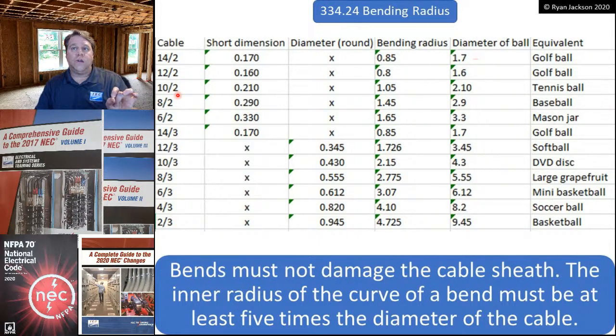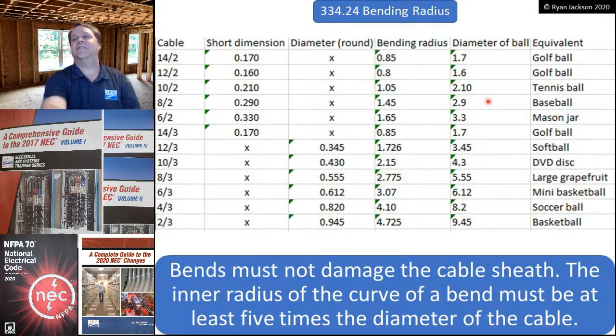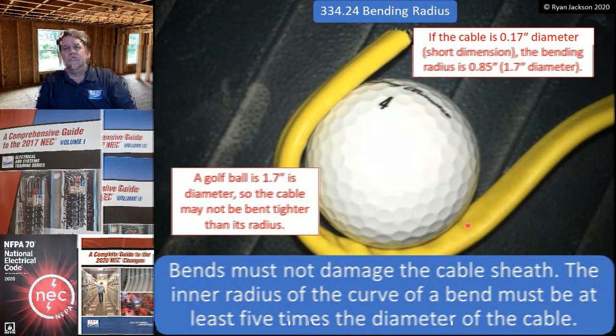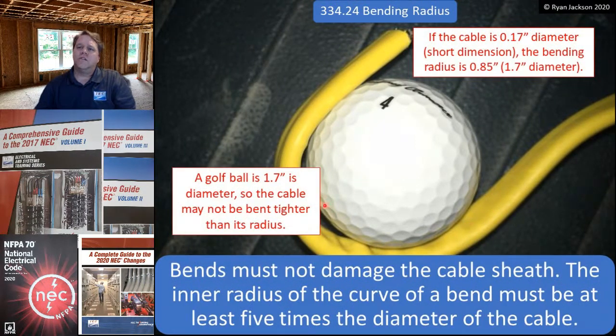If I had 10-2, that's similar to a tennis ball. So if this was 10-2, don't bend it tighter than a tennis ball. And baseball for 8-2, and then I started really stretching it. I'm like, okay, 8-3 is a grapefruit, and 2-3 is a basketball. But anyway, exceeding the bending radius for smaller cables, I think, is actually more difficult to do than I initially thought. This is not a violation, it complies. That is not an excess bending radius. Even though you can start to see the cable starting to ripple down at the bottom, that's still not a violation.